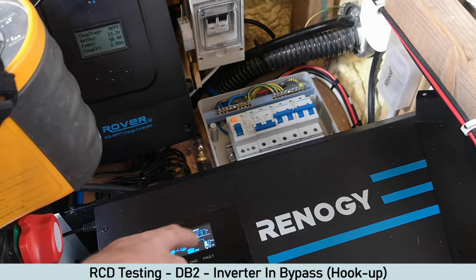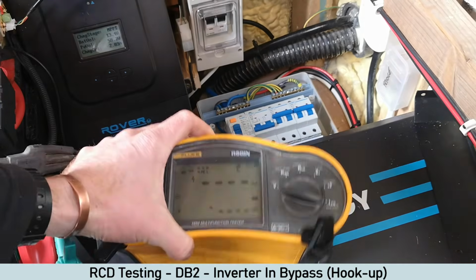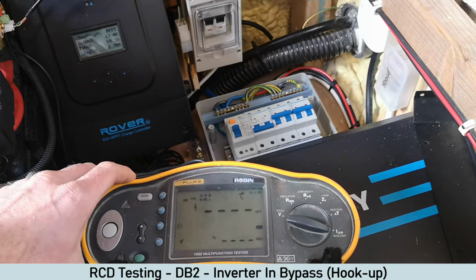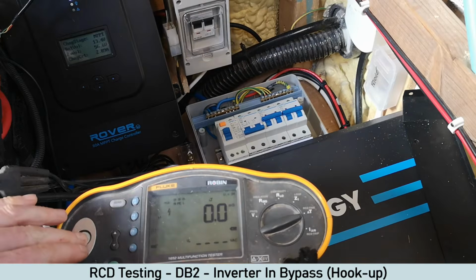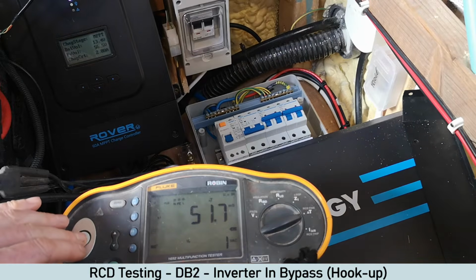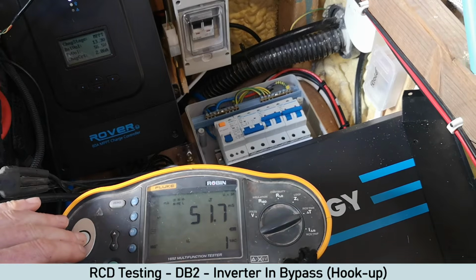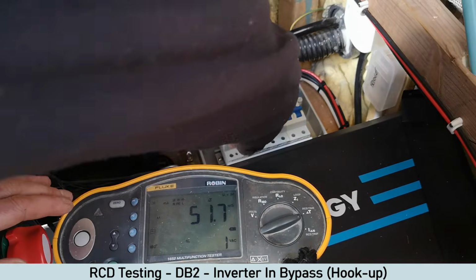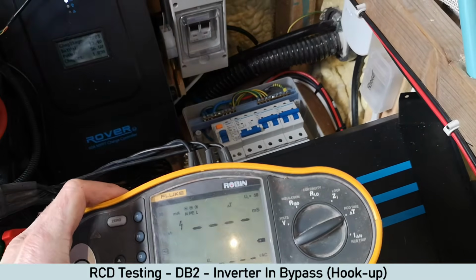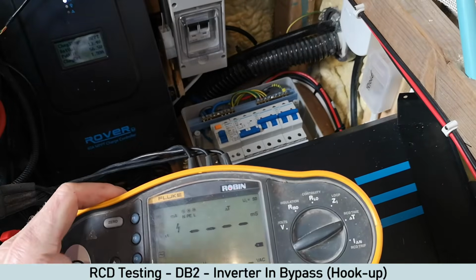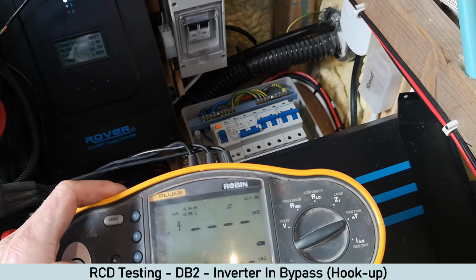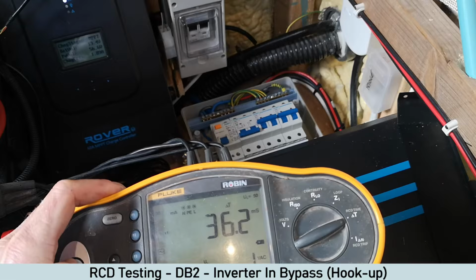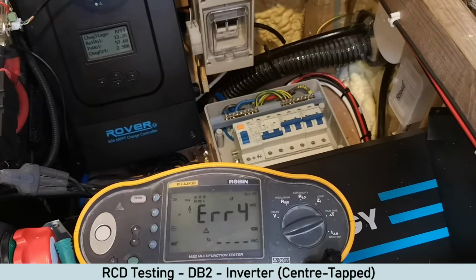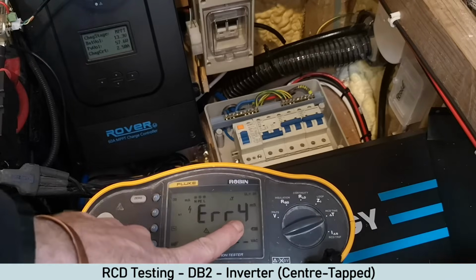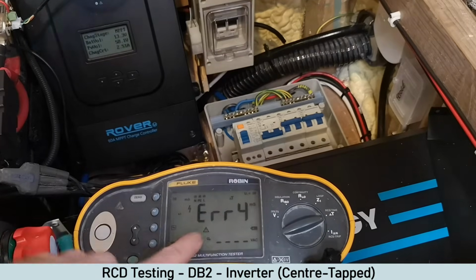So I'm on hookup, so obviously you can see there it's in bypass. Power's on to the tester. There we go, 51.7, so that's less than 300 milliseconds. I'll do that test again, and I'll show you here a bit closer, and you can see that obviously the RCD is on. If I do, there we go, 36.2. I'll turn it on. Now we're getting an error.